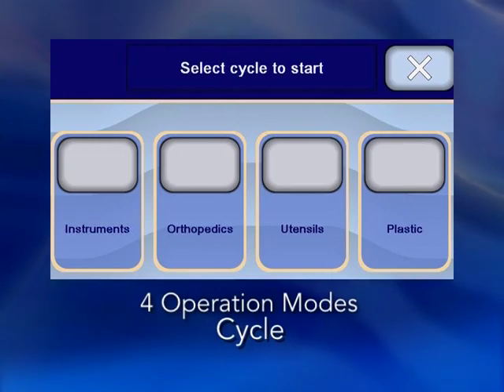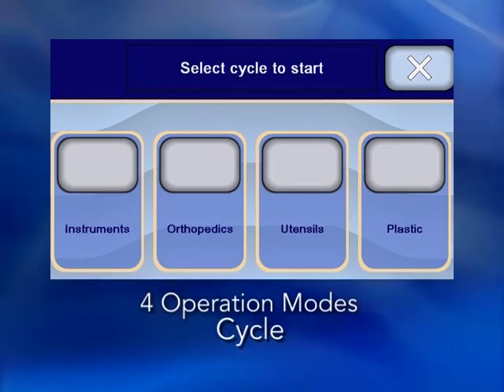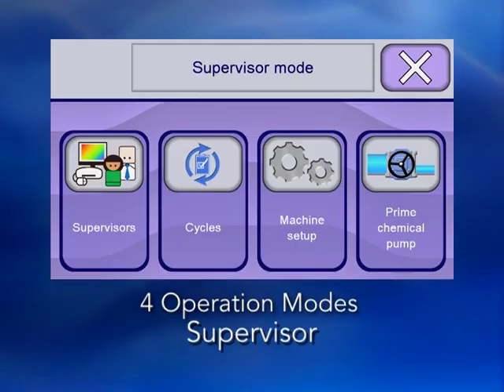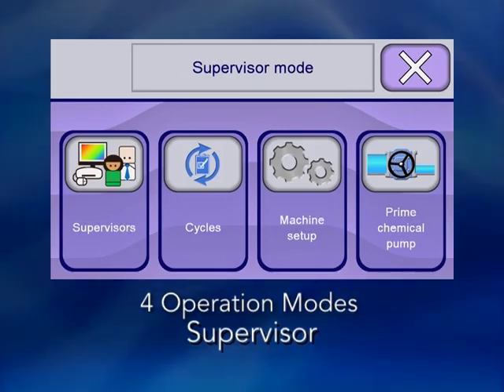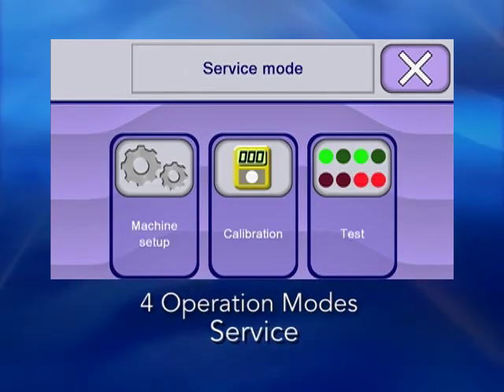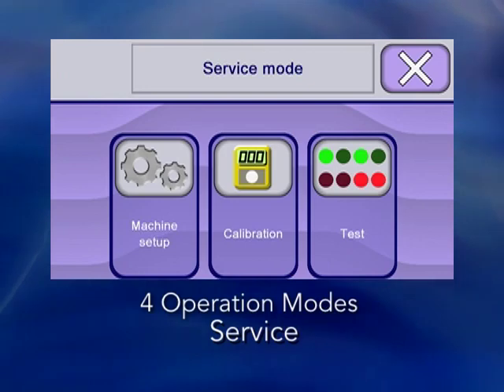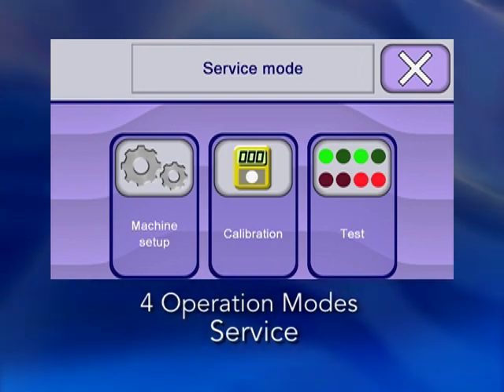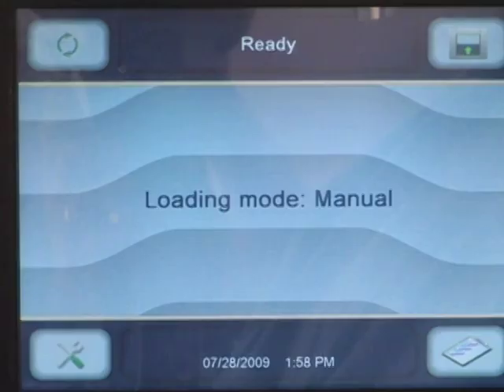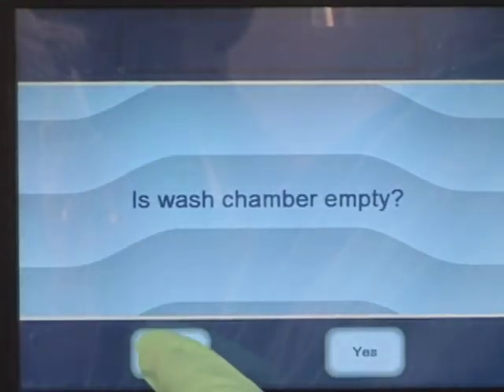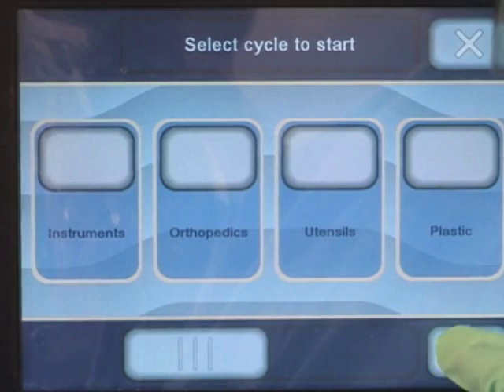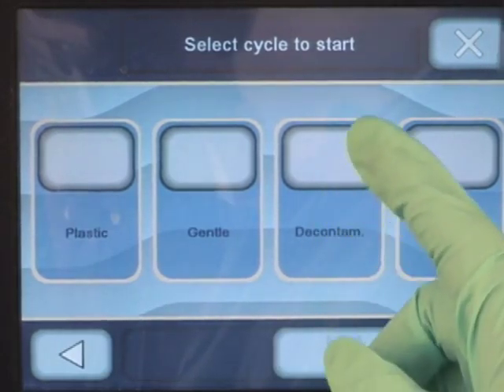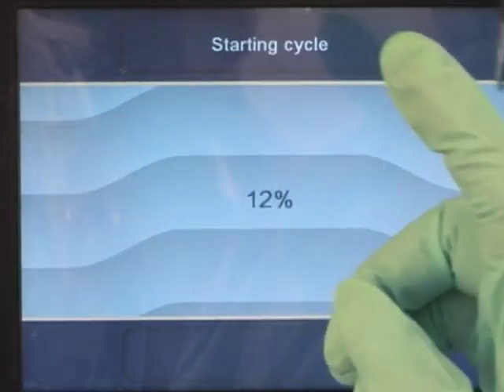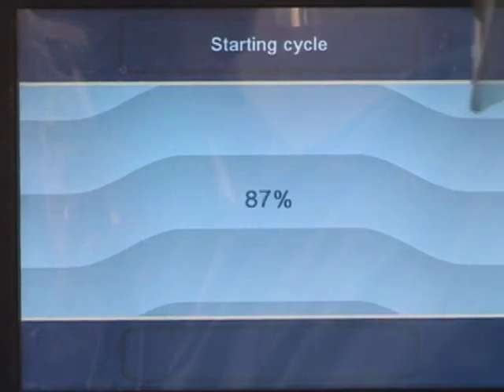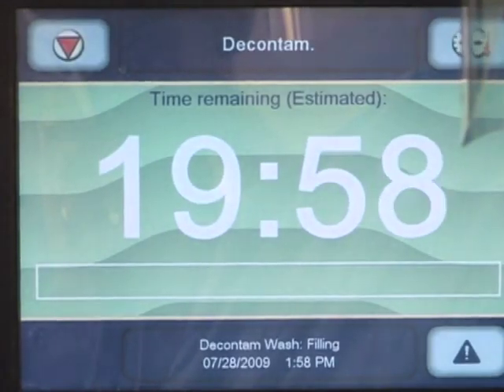Cycle, which is used to initiate a processing cycle. Supervisor, which allows your supervisor to customize or create cycles. And Service, which allows a Steris service technician to perform maintenance and troubleshoot any equipment issues. To initiate a new cycle, select Cycle from the Ready mode on the control screen. Select the appropriate cycle. Use the arrows to see additional choices. Remember to choose the gentle cycle when processing delicate surgical instruments.